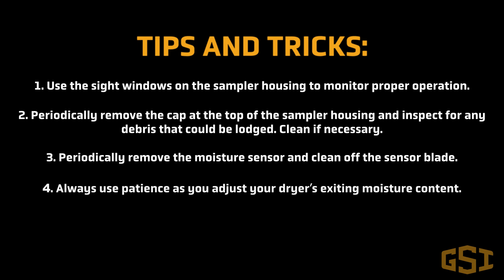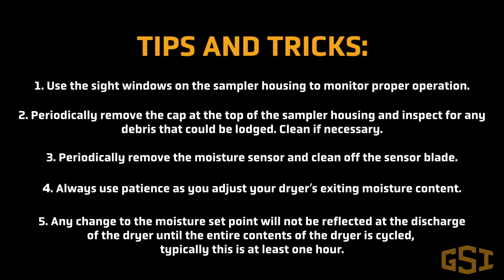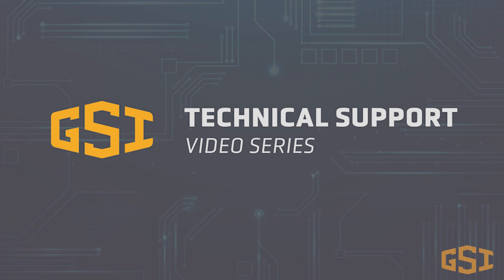Periodically remove the moisture sensor and clean off the sensor blade. Always use patience as you adjust your dryer's exiting moisture content. Any change to the moisture setpoint will not be reflected at the discharge of the dryer until the entire contents of the dryer is cycled — typically at least one hour.